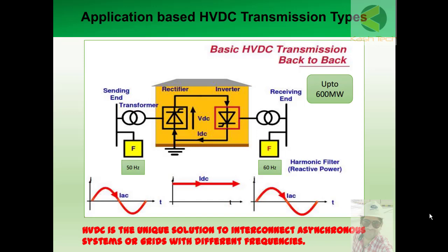Here you can see that one network is supplying power at 50 Hz whereas the other network is generating power at 60 Hz. If you want to connect these with an AC transmission line, it will not be possible because two different frequencies cannot be connected together. That is why the DC link is used here — AC is converted to DC, and then both can be connected together at the same voltage levels.